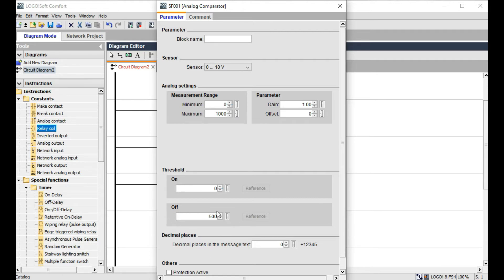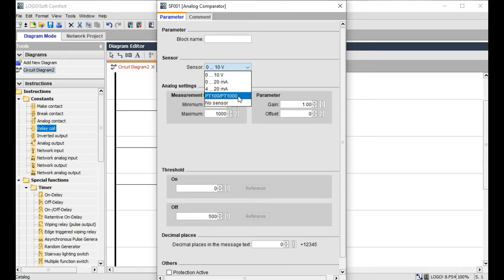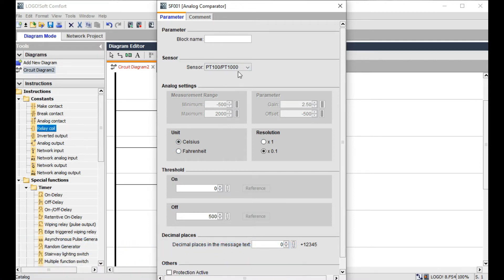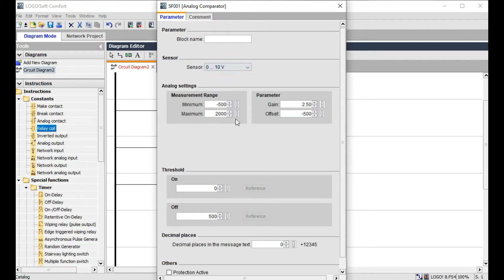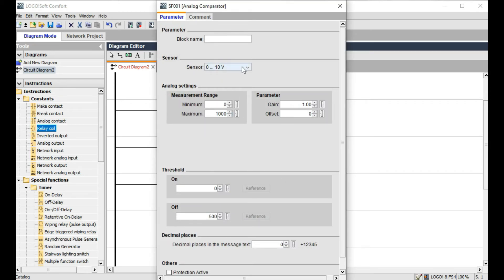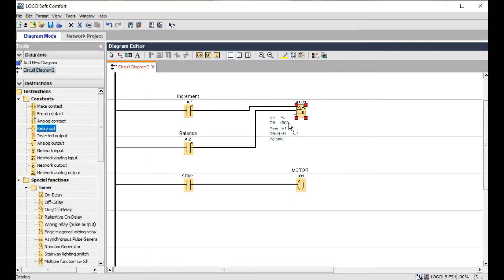When you increment the value, the balance sensor goes from zero to 500 as our set point. Zero to 500 — in this range the motor will be on. When this value crosses 500, the motor will be off. The sensor value is 4 to 20 milliampere. This depends on PT-100 or PT-1000. In my previous video RTD, that was absolutely PT-100, and the fixed value range is minus 500 degrees to 2000. This is our zero to 1000 value for zero to 10 volt, or zero to 500 bits for zero to 5 volt.